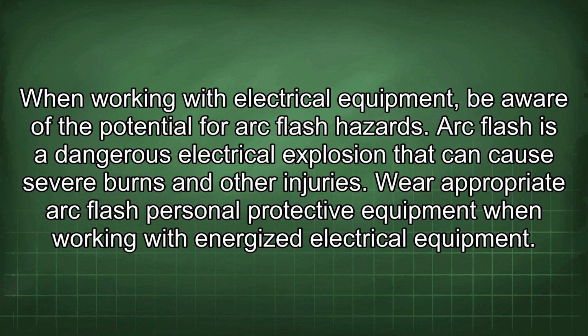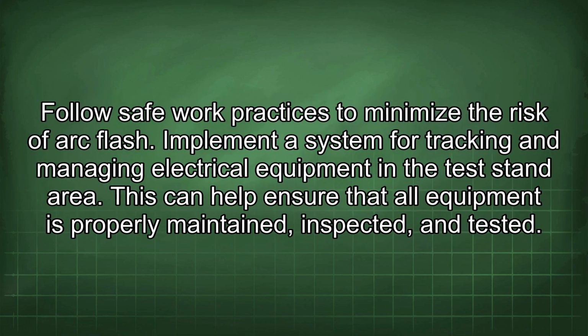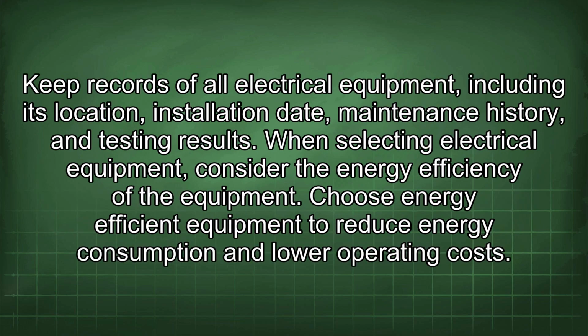When working with electrical equipment, be aware of the potential for arc flash hazards. Arc flash is a dangerous electrical explosion that can cause severe burns and other injuries. Wear appropriate arc flash personal protective equipment when working with energized electrical equipment. Follow safe work practices to minimize the risk of arc flash. Implement a system for tracking and managing electrical equipment in the test stand area. This can help ensure that all equipment is properly maintained, inspected, and tested. Keep records of all electrical equipment, including its location, installation date, maintenance history, and testing results.